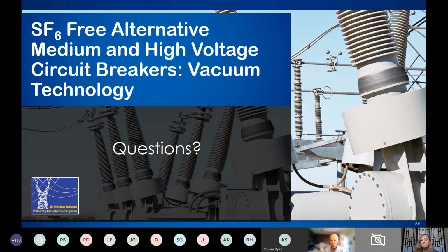I think it was Joseph that was just speaking. Similar to PPL, we've had vacuum breakers on our distribution system for many years, so we're familiar with working with vacuum. One thing we're looking at implementing is a vacuum integrity test, and we're still working with one of our manufacturers on developing that. Basically it would be like a high pot test, just to make sure that during transit and installation something didn't happen to break the vacuum seal. Other than that, it's pretty standard - we're using the same commissioning processes as we would for SF6, to my knowledge. I'm not as familiar with the maintenance side, so I don't know all the details, but I know the vacuum integrity test is one thing we're looking at.